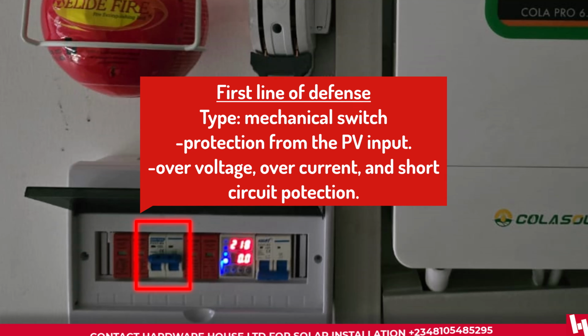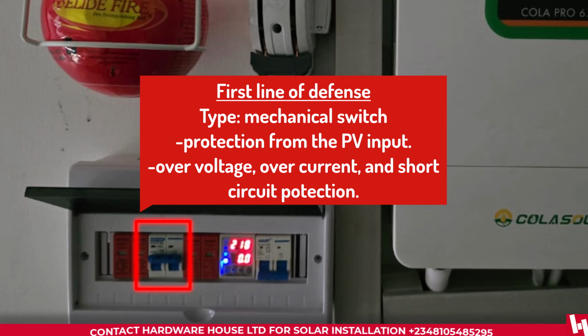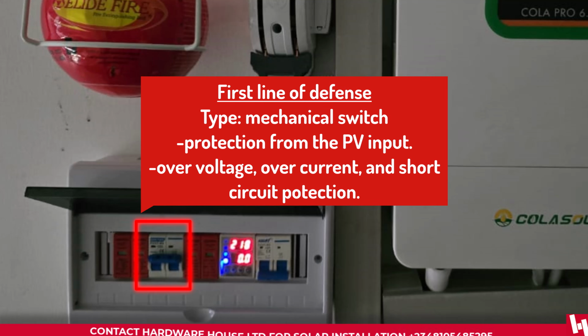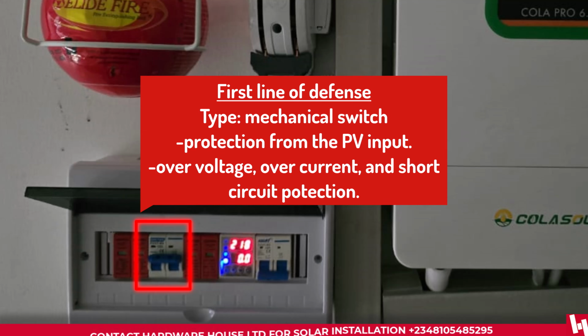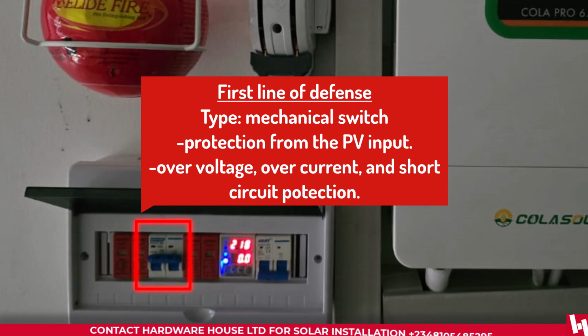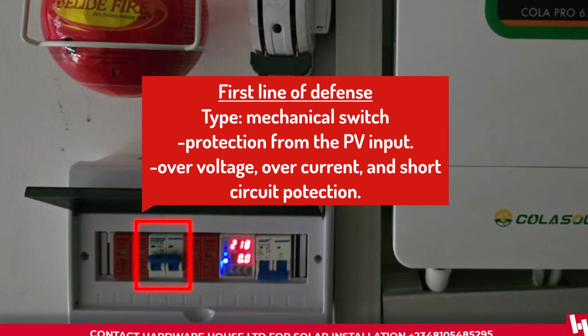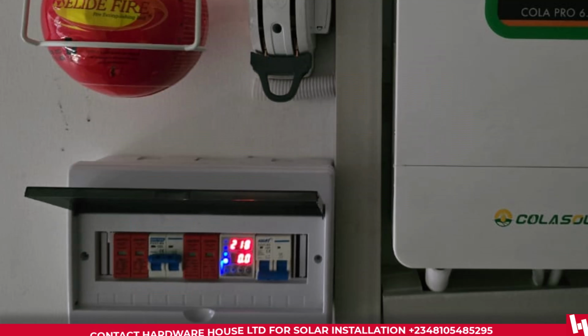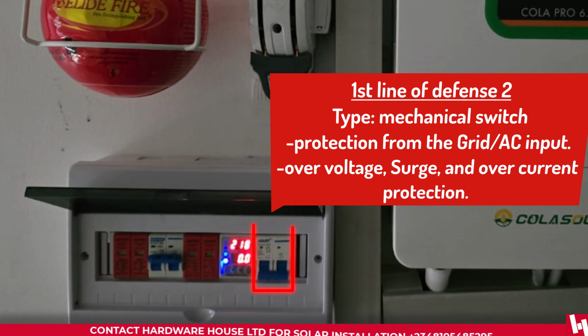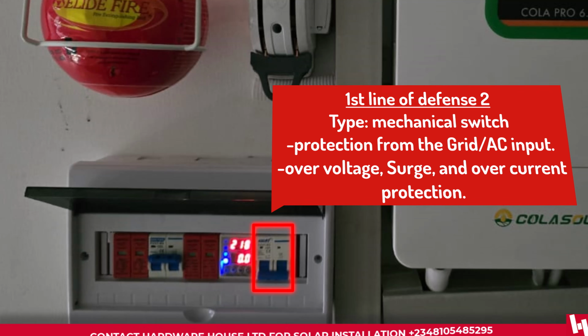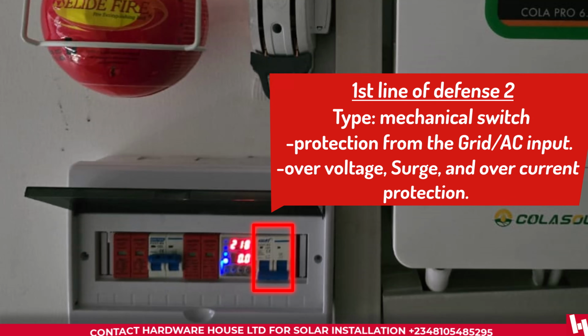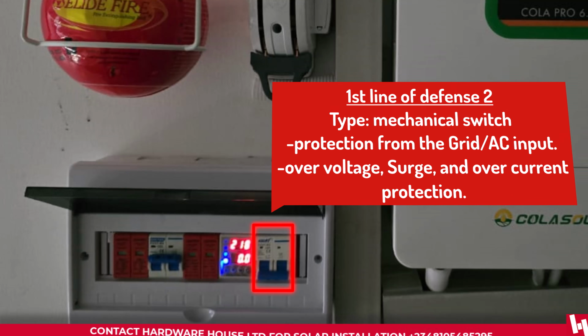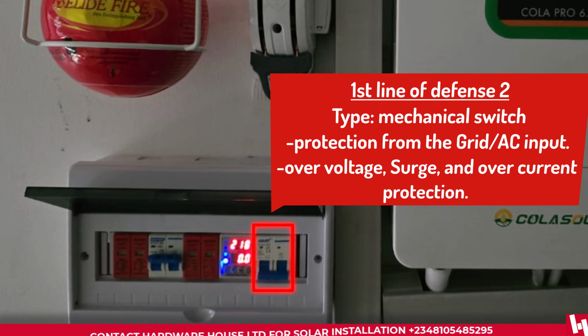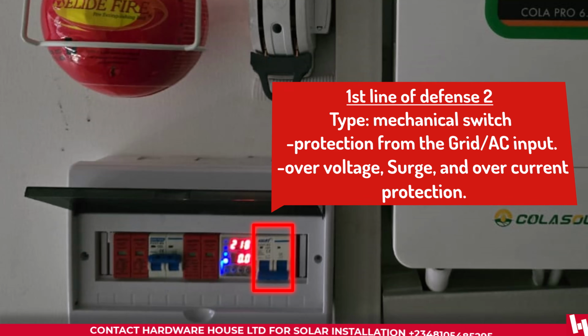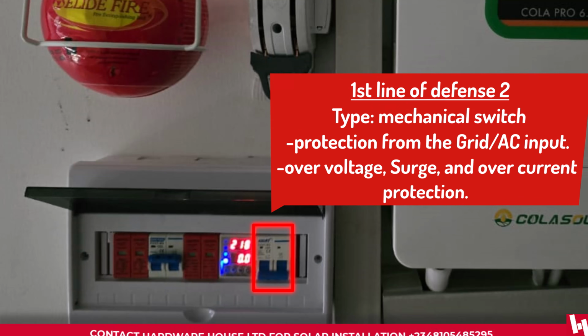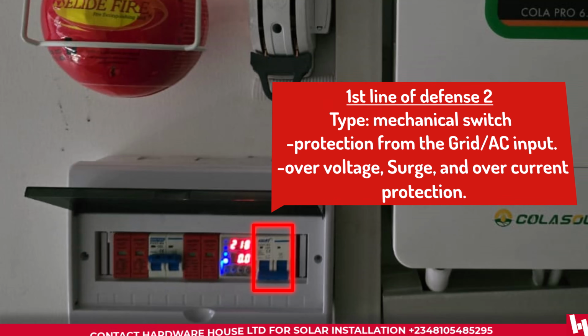But if somehow it escapes and somehow miraculously enters, the inverter also has its own power management system, and it's going to shut down the whole setup, and the power would not even get to the battery, more or less the house. And then the second breaker, grid input for charging the inverter with electricity. If there is a surge from the grid, these guys can be really funny. But whenever there is a surge coming from the grid, the breaker for the grid is going to flip and disconnect the inverter, and by so doing disconnecting the entire system.